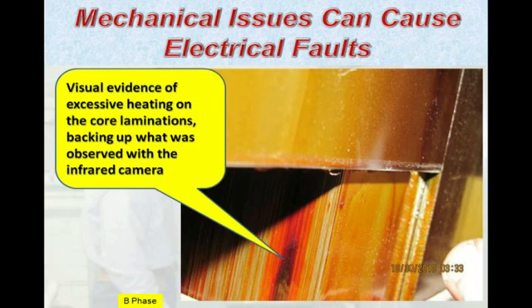Once we started looking at the laminations within the core, we saw the visual evidence of this heating. Of course, we saw it with the camera as well. But you can clearly see the blackened area on the core here with the vertical laminates where the thermal energy was present. And that backs up more or less what we were seeing with the infrared camera. So there's already thermal damage that has taken place within this transformer. Now that in and of itself is not enough, again, to pull the unit out of service, replace it, or recondition it, but we can see that damage is occurring, and this is validating what we recorded with the Ultra Probe.